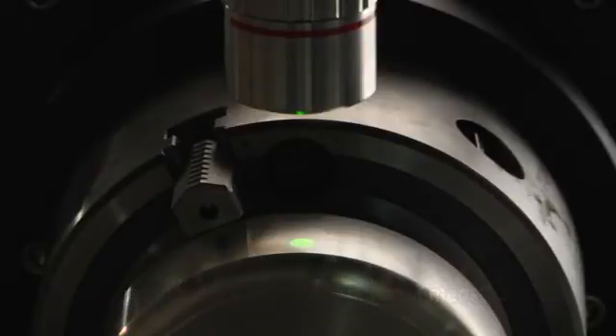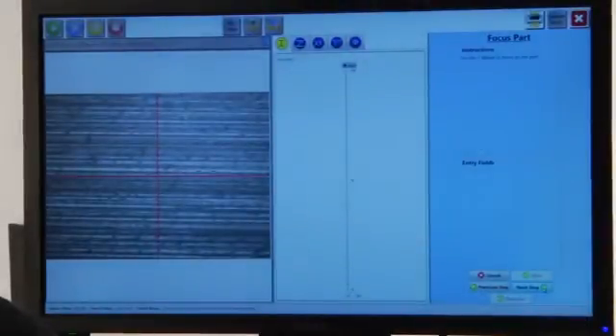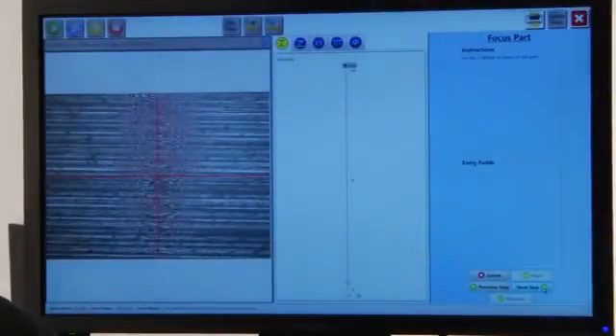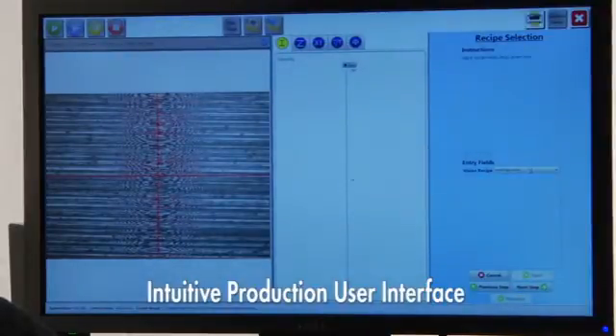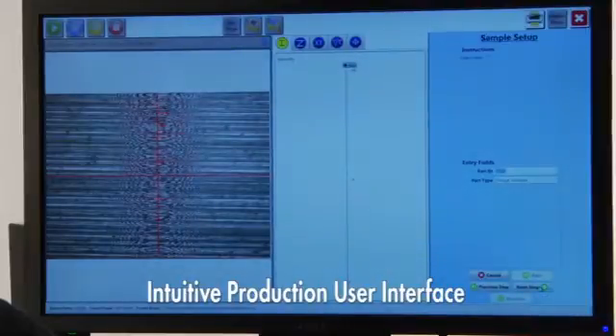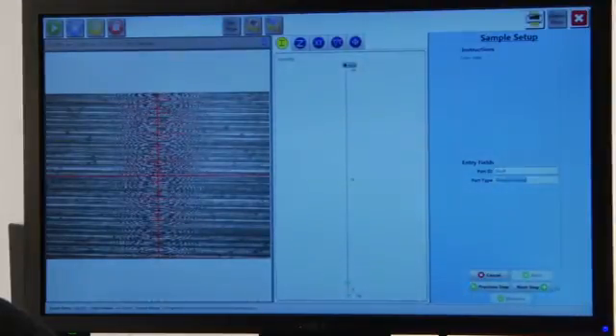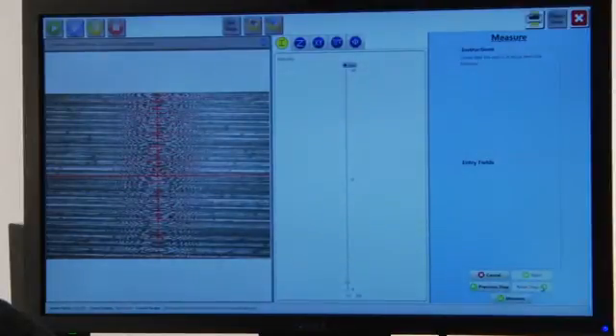The NP-FLEX LA features an easy-to-use production interface that provides reliable global lead angle measurements for QA and QC environments. A dedicated wizard walks operators through setup and measurement, generates customized reports, and uses pass-fail criteria to locate and discard nicks, burrs, and scratches on the measured surface.